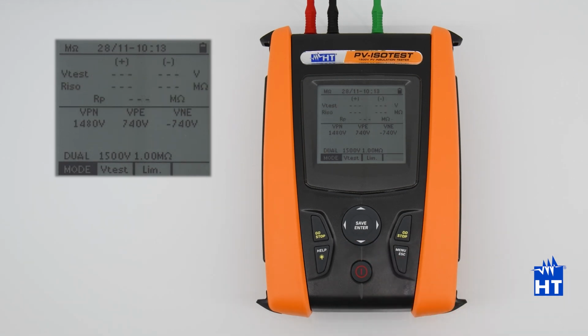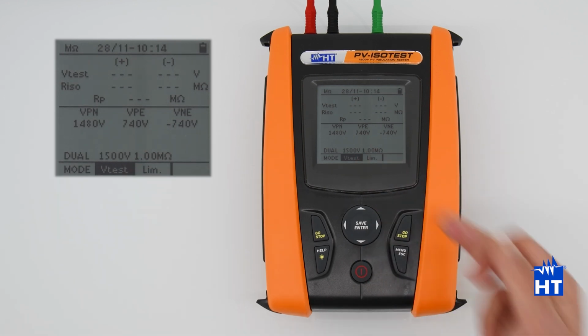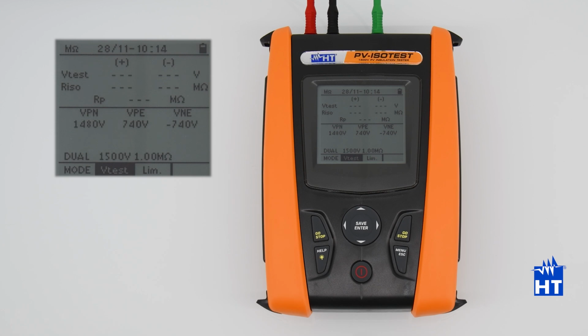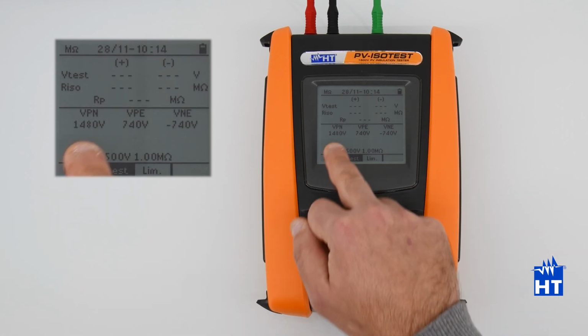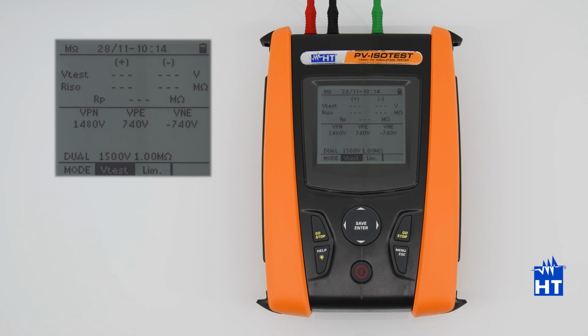So, now we can select the test voltage. In this case, we are selecting 1500 volts because our nominal voltage is about 1500 volts. As you can see from the voltage between P-N, we have 1480 volts. And we have also the voltage between positive and earth and negative and earth.